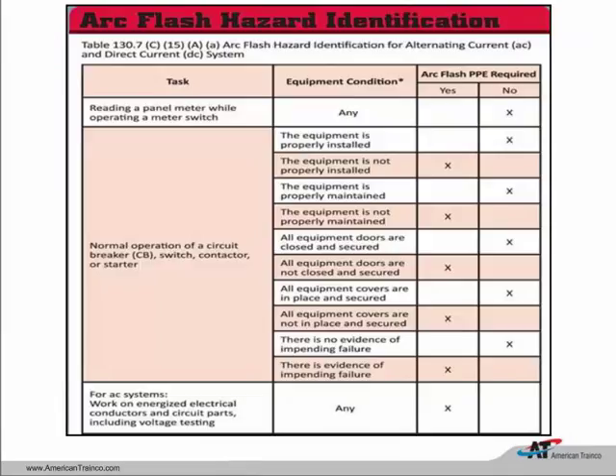Now we get to the tables that are going to give us an idea if we need arc flash PPE clothing or not. So these are the yes or no tables. The first one that I would like to take a look at is the normal operation of a circuit breaker. So to begin with, we understood back in Article 110 that to operate that circuit breaker normally, it had to be installed properly, it had to be maintained properly. So all those questions are now here. We see all these questions in this table now. So let's take a look at just the normal operation of a circuit breaker.